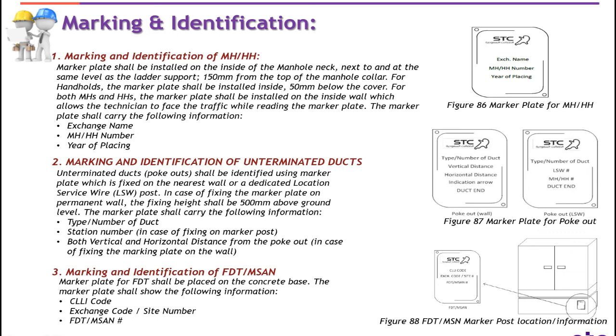Number one: marking and identification of manhole and handhole. Marker plates shall be installed on the inside of the manhole neck next to and at the same level as the ladder support — 150 mm from the top of the manhole collar. For handhole, the marker plates shall be installed inside 50 mm below the cover. For both manhole and handholes, the marker plate shall be installed on the inside wall which allows the technician to face the traffic while reading the marker plate.